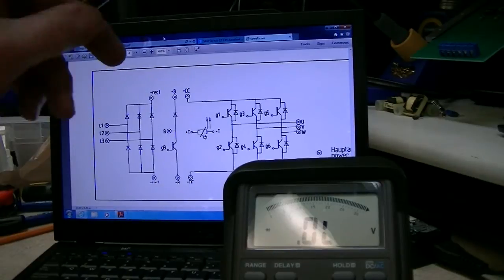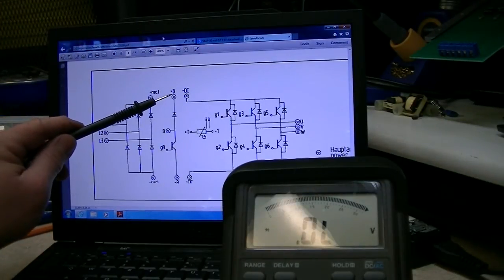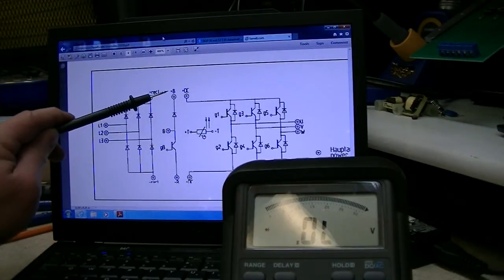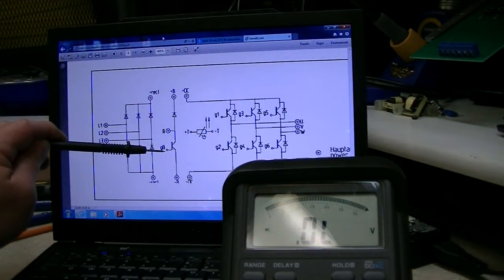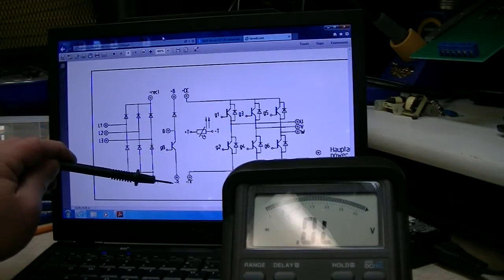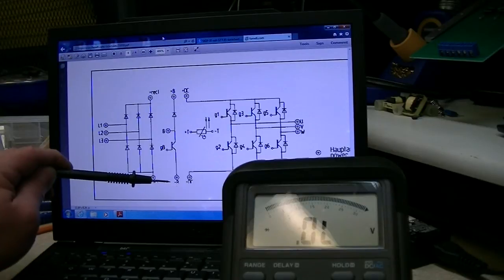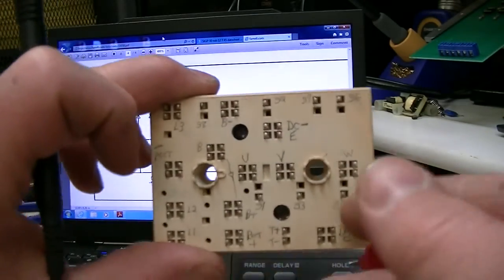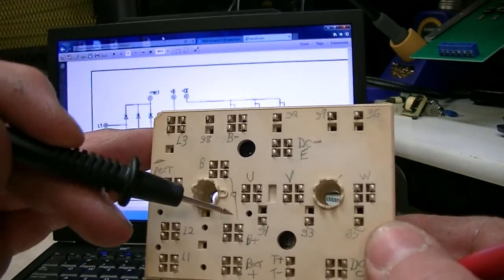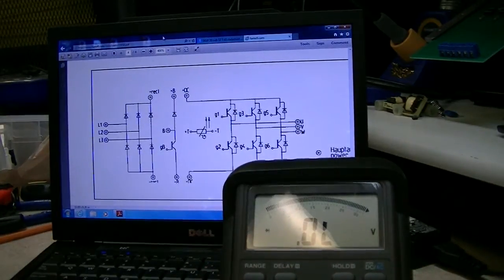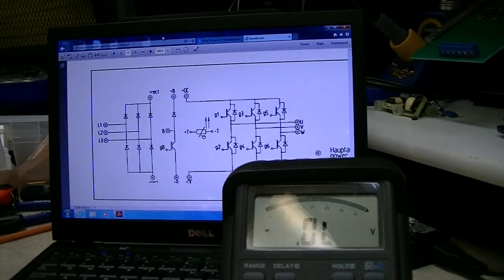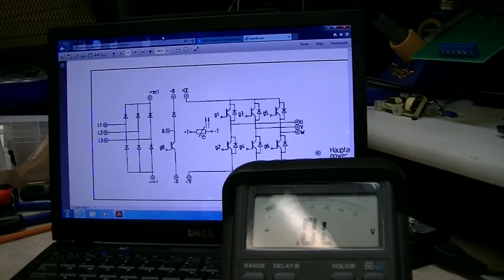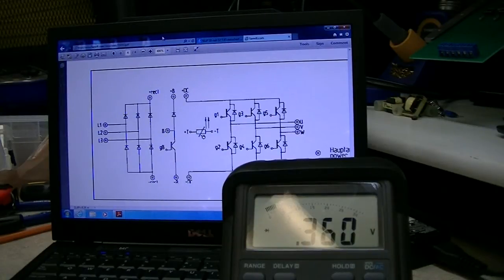Okay, next up is this first IGBT. This one here is for the brake chopper. That's why it's labeled B+, B, G for gate, B for brake. And I assume that little mess right there is B minus. So let's see. Notice I drew a little diode on there so I knew about where that was. Let's go across that diode one direction and the other direction.